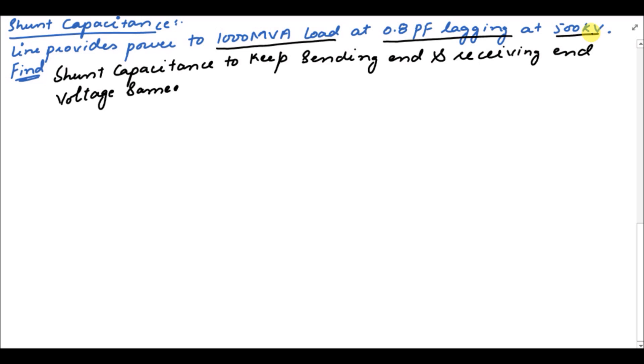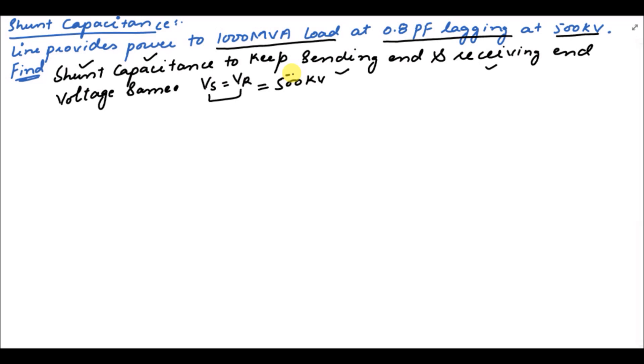The load is to be provided by the transmission line and the voltage level at the receiving end is 500 kV. What we have to find is the shunt capacitance to keep the sending end and receiving end voltage the same, so we want Vs equal to Vr, both equal to 500 kV. We assume the values from the last example: Zc the surge impedance is 290.43 and beta·l is equal to 21.641, where beta is the phase constant and l is the length of the line.